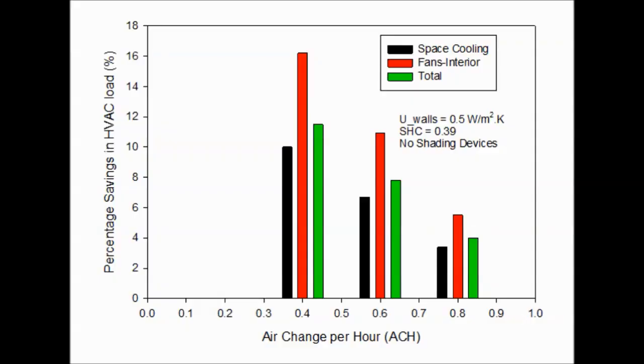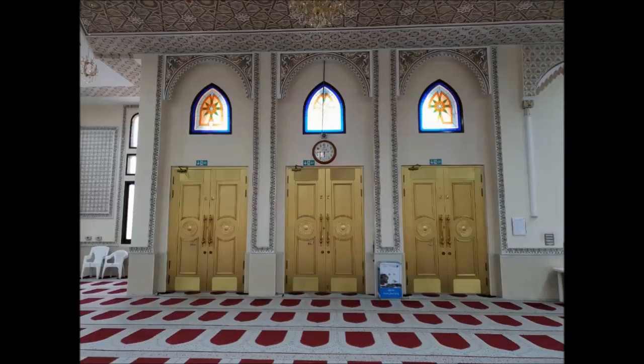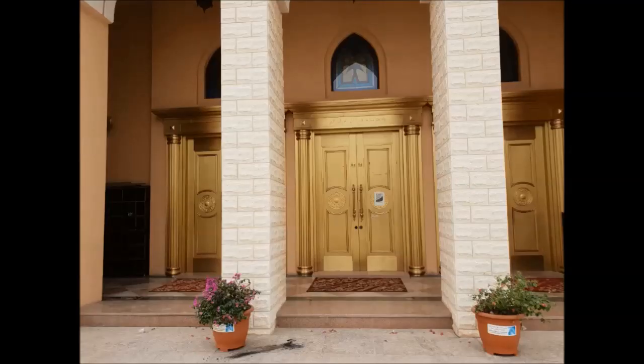Before attempting to calculate the actual rate of infiltration, the effect of lowering the value of air change per hour was simulated using HAP software. The results showed a great impact of lower values of ACH on the building cooling load. Recent advances in windows glazing technologies can limit infiltration to the minimum in cracks around windows, so the focus of infiltration calculation will be on the building doors.